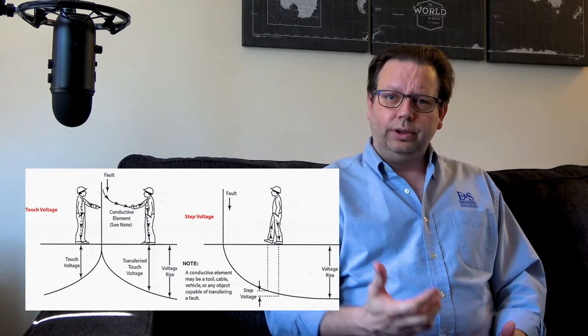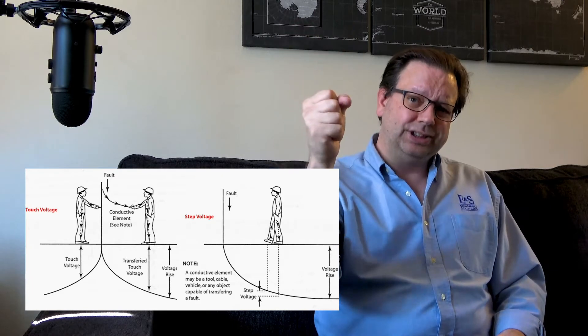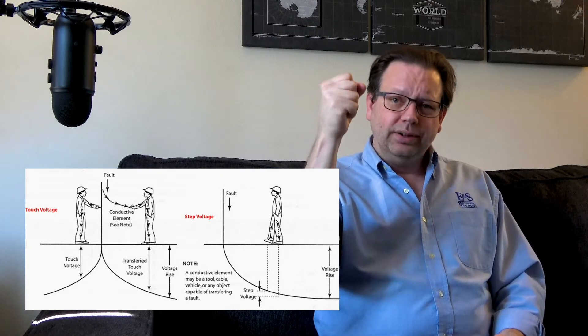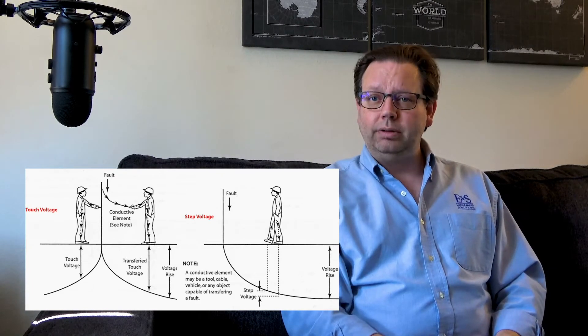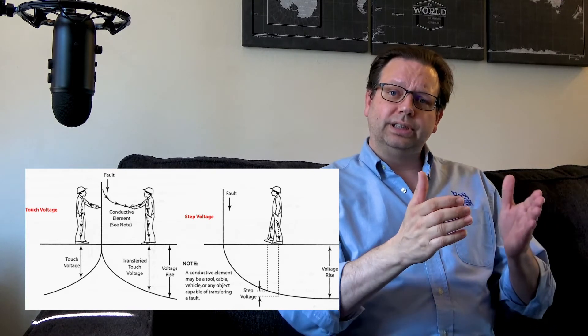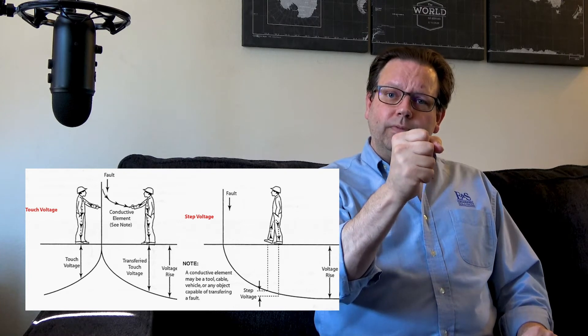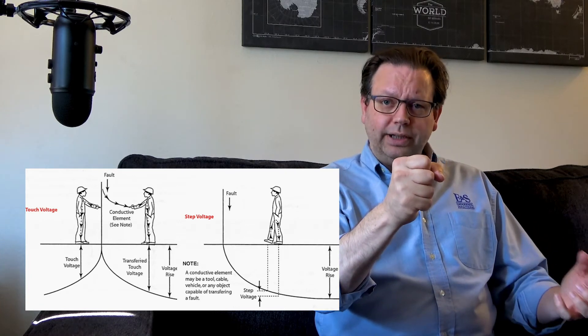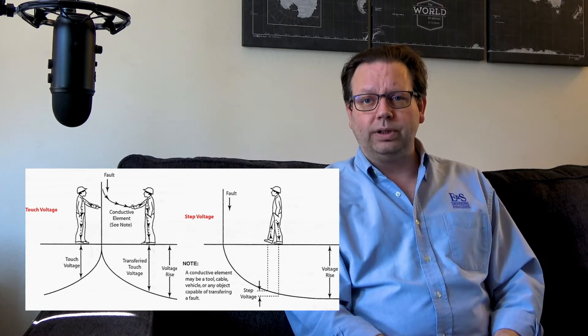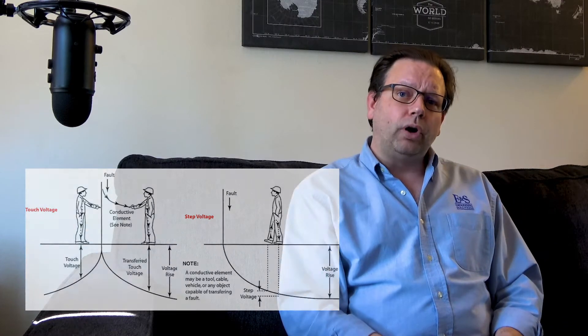The other voltage that can kill you is if you happen to be touching this tower when this occurs. The difference between your hand and your feet can be enough to kill you. If your hand's at 1,000 volts but your feet are at near zero, that's a 1,000-volt differential traveling right through your heart, and that causes fibrillation currents to occur. That's what we call touch voltages, and that can be very dangerous, more dangerous, typically, than step voltages are.